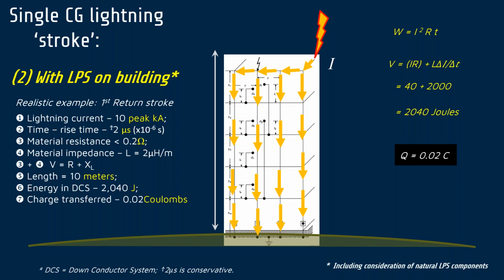What that is saying is that if you have a lightning strike with a very high electric field, it will be intercepted by the finials that you put on the roof or your mast, whatever you're putting up there to intercept it. If you have a weaker lightning strike that has a lower electric field, we are safe to 5% guarantee that it will sneak past.